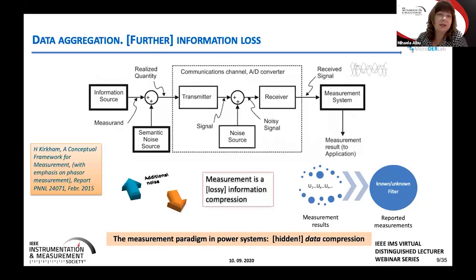But the story does not stop here, because there is further information loss. Again, copying a kind of analog way of data compression, the results of measurements are not made available as they are, even in the form of information concentrators or sample values. Usually, further decimation of the measurement results is performed, using a known or unknown filter, to achieve lower reporting rates of those measurement results. As you see, I use this term reporting rate from the PMU realm.